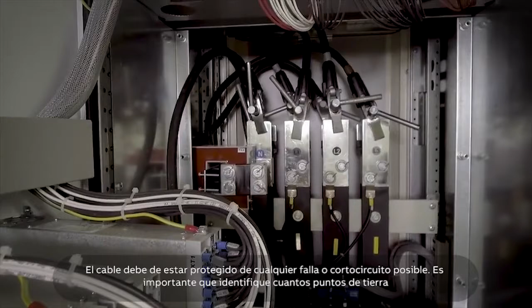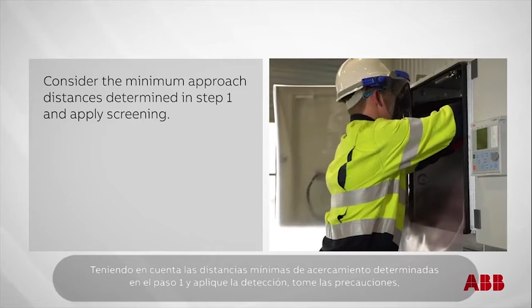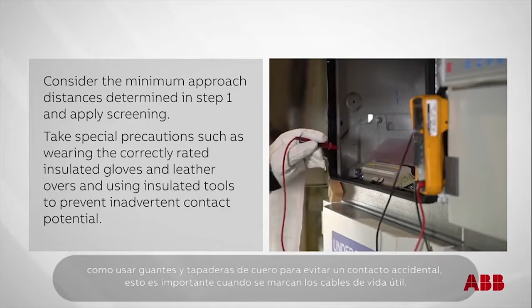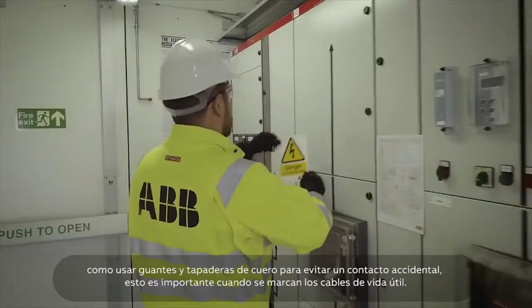Step 6. Protect against adjacent live parts and take special precautions when close to bare conductors. Consider the minimum approach distances determined in Step 1 and apply screening. Take special precautions such as wearing the correctly rated insulated gloves and leather overs and using insulated tools to prevent inadvertent contact potential. This is especially important when marking live components or cables or while placing protective barriers or screens around the area as you prepare to do the job.